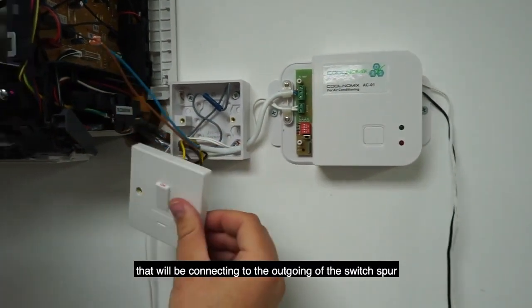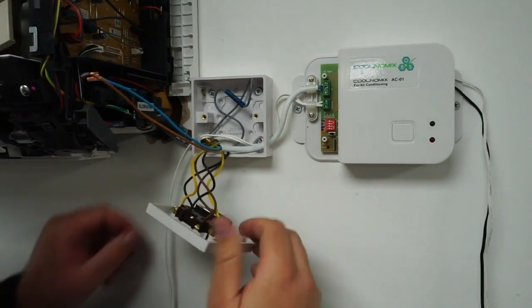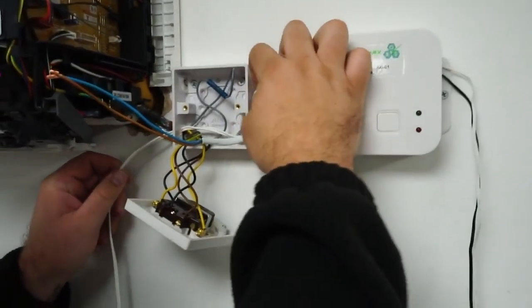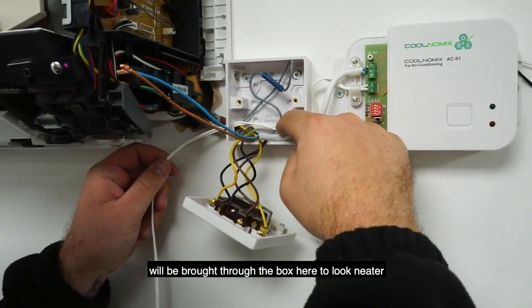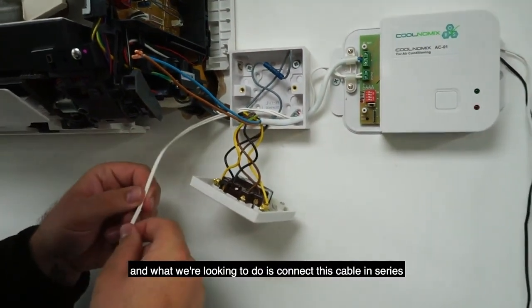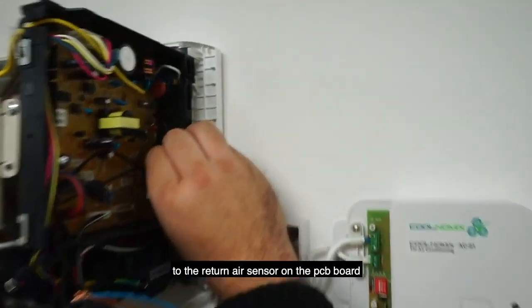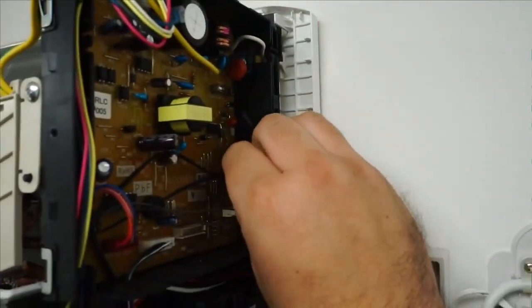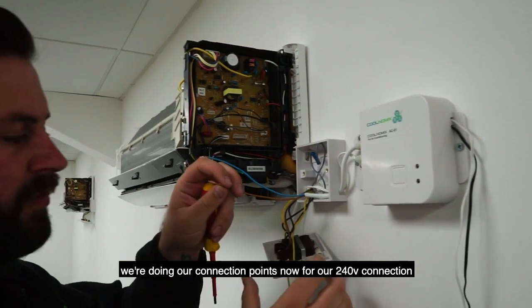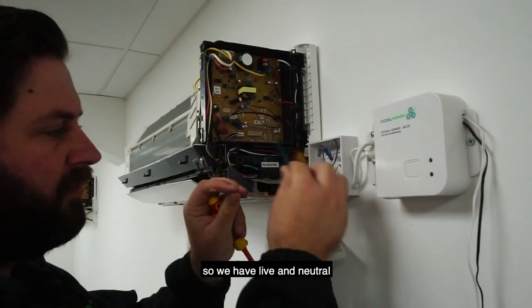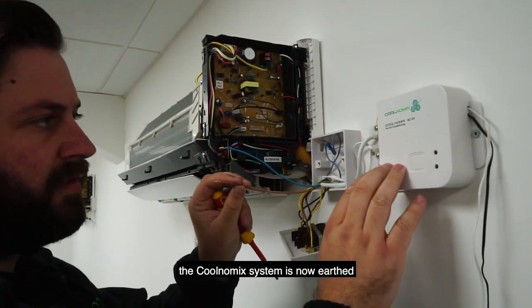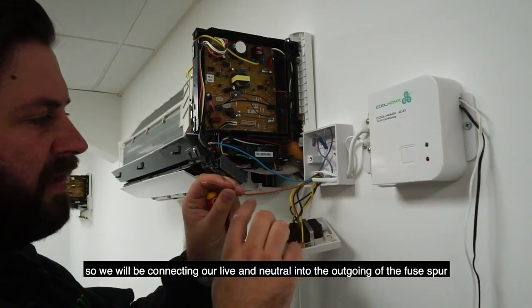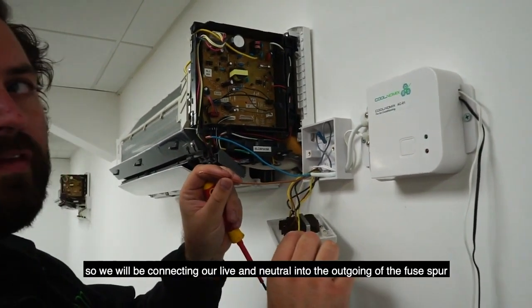Connection point into the switch spur. That will be connecting to the outgoing of the switch spur. The relay connection will be brought through the box here to look neater. And what we're looking to do is connect this cable in series to the return air sensor on the PCB board. We're doing our connection points now for a 240 volt connection. So we have live and neutral. The Coolnomix system is now earthed. So we'll be connecting our live and neutral into the outgoing of the fuse spur.